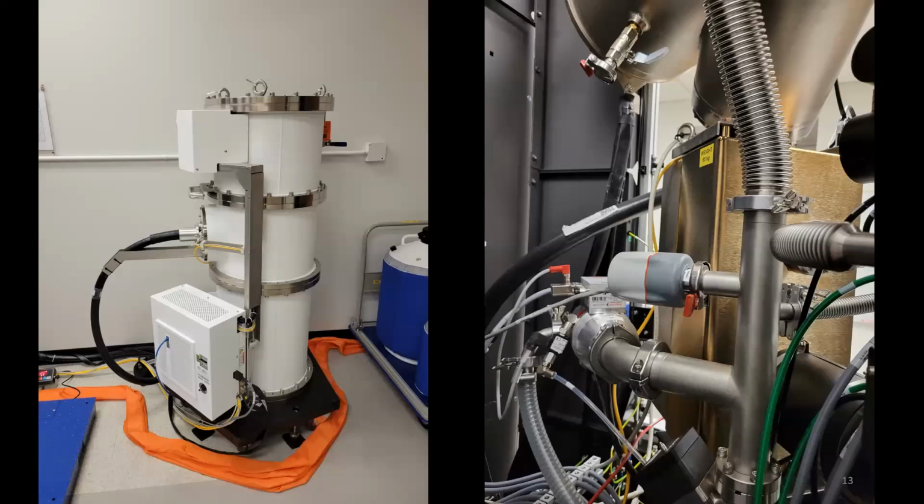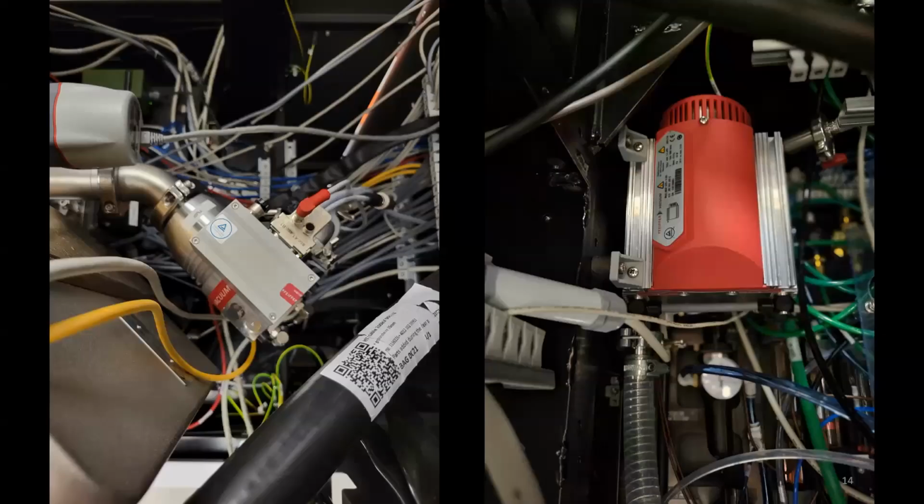This is the turbo pump. So that itty bitty little guy, he's just a cute thing. He's like that big. That does all of the turbomolecular pumping. So that's our first rough pump, and then our second rough pump, let's see if we can get there, is down here. This little guy is a roots pump, Pfeiffer Vacuum, oil-free roots pump.